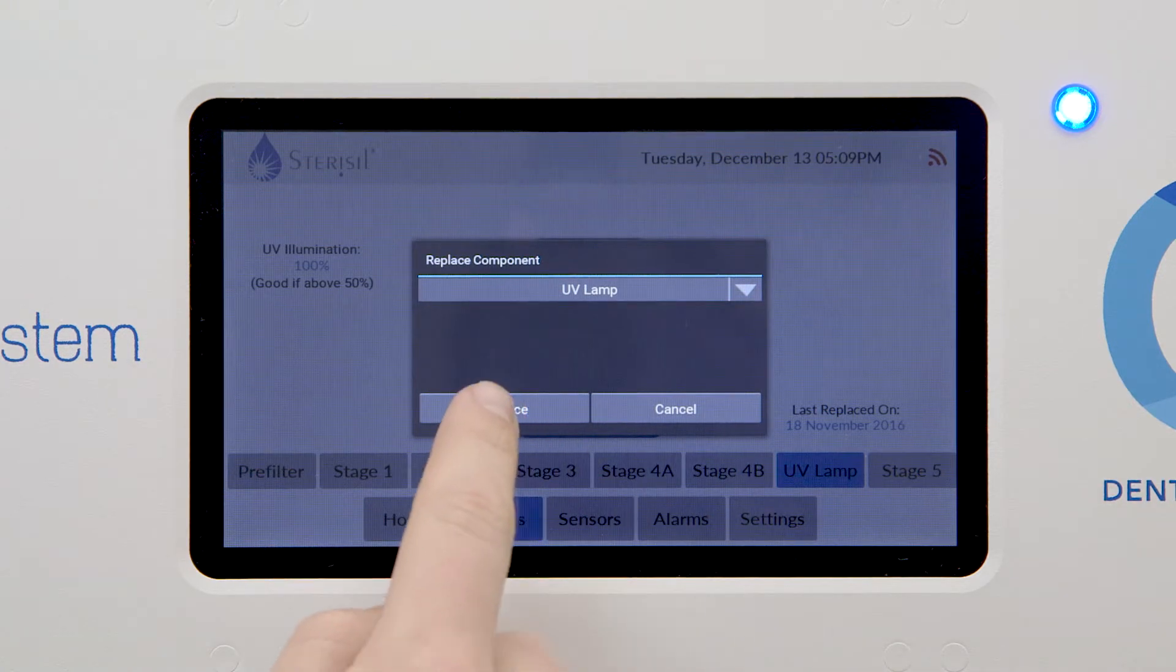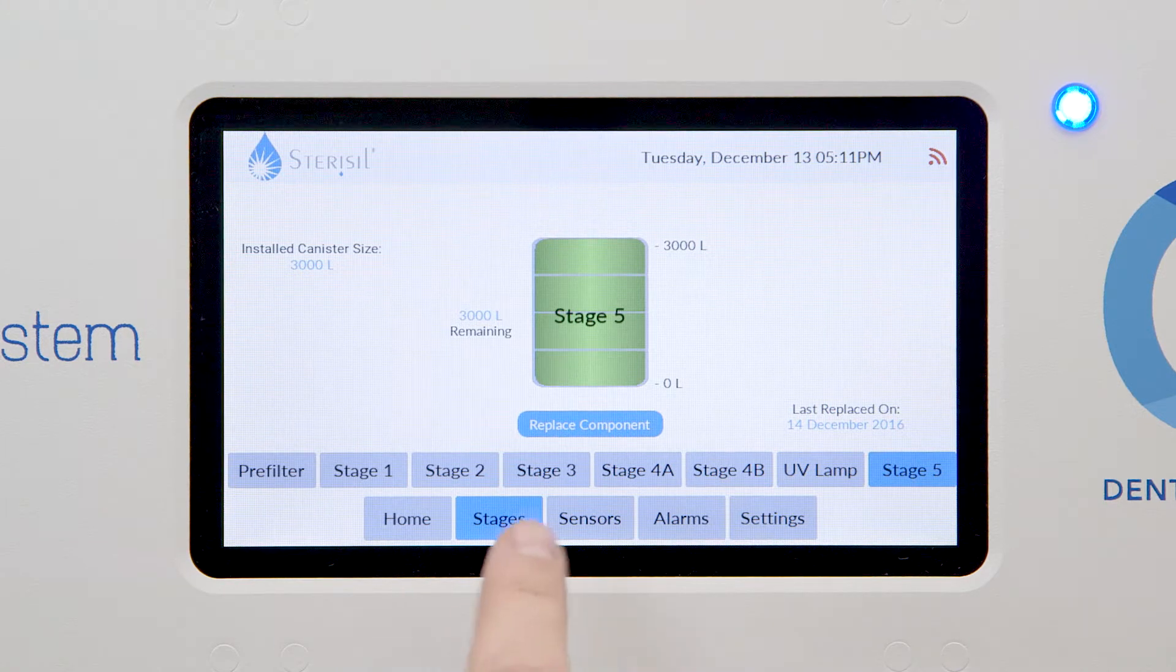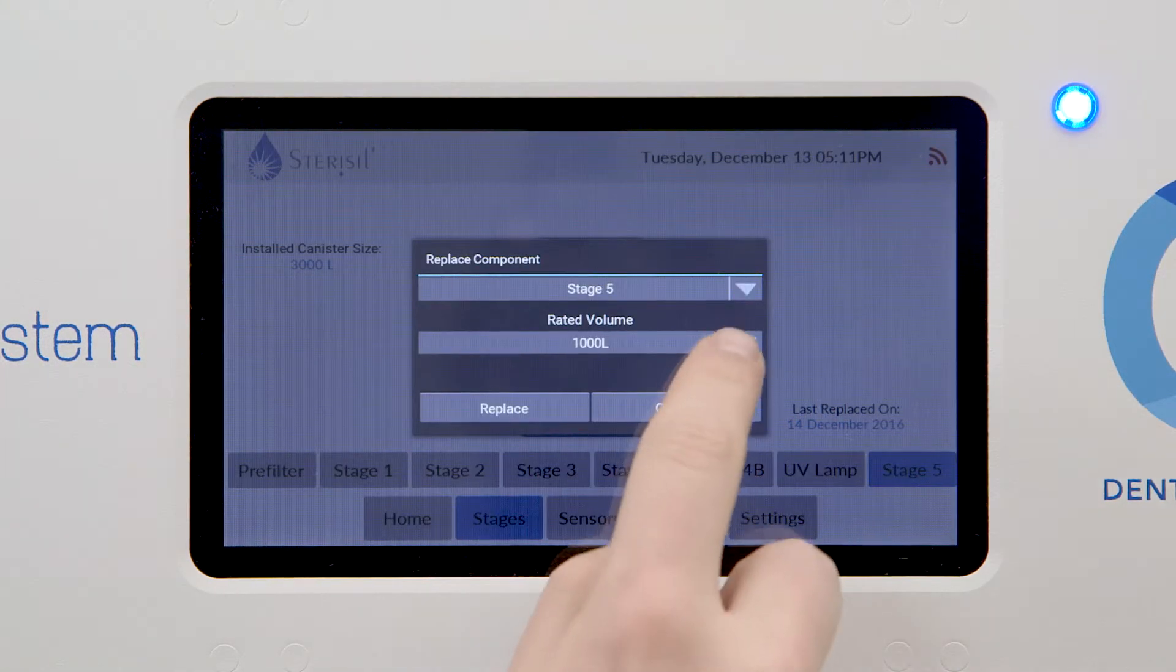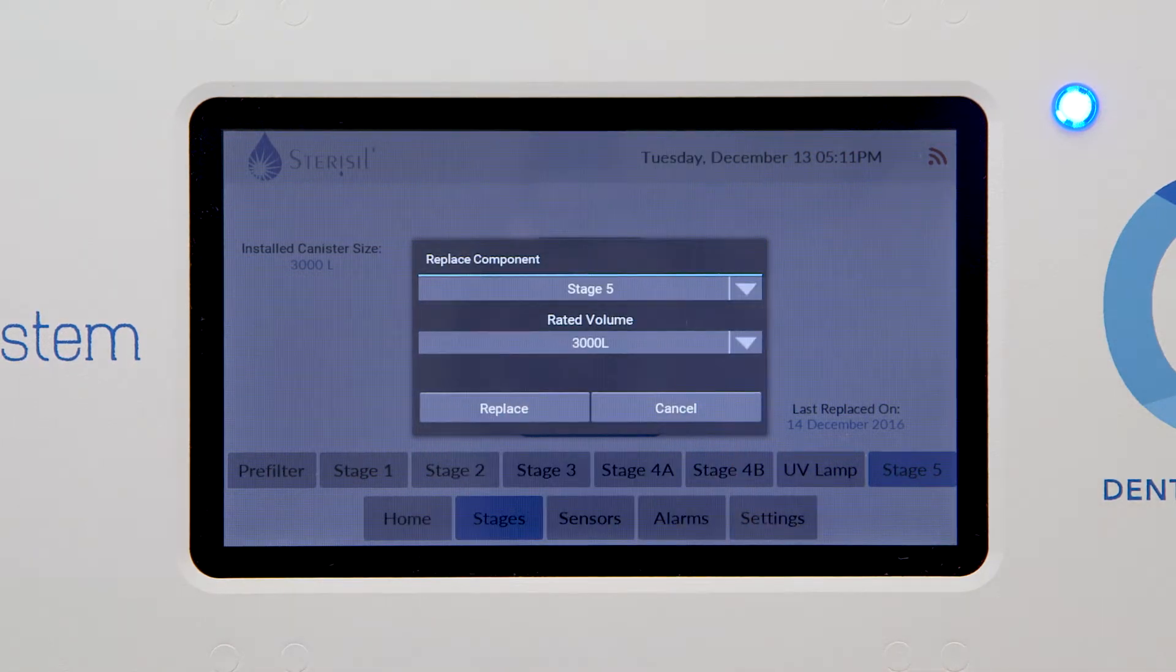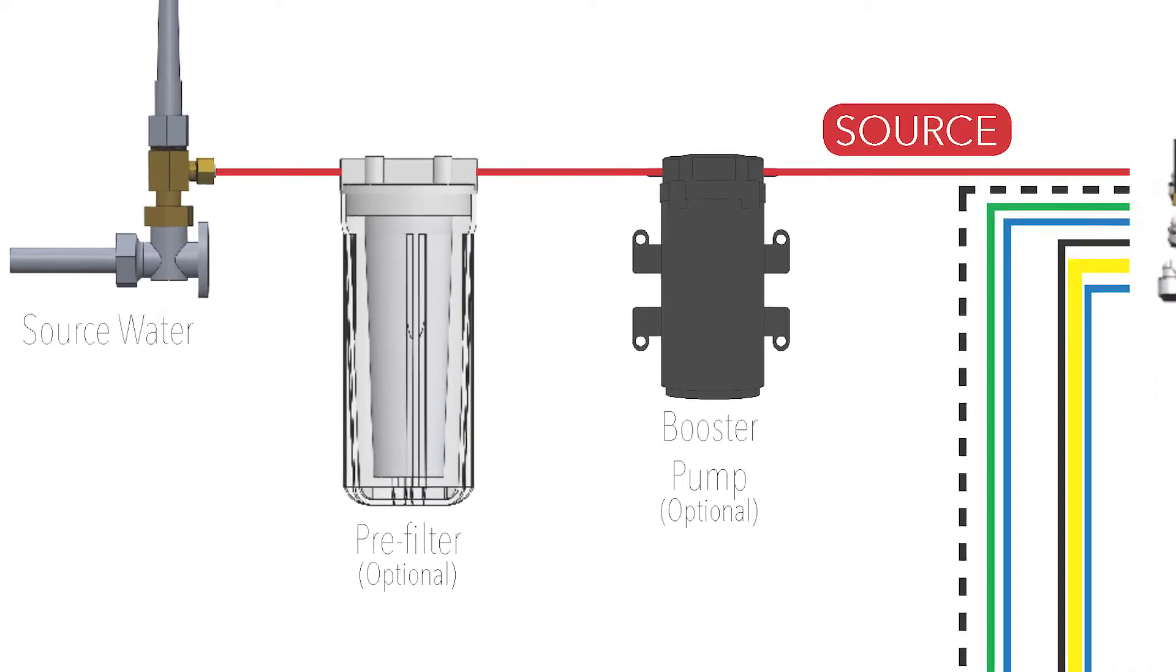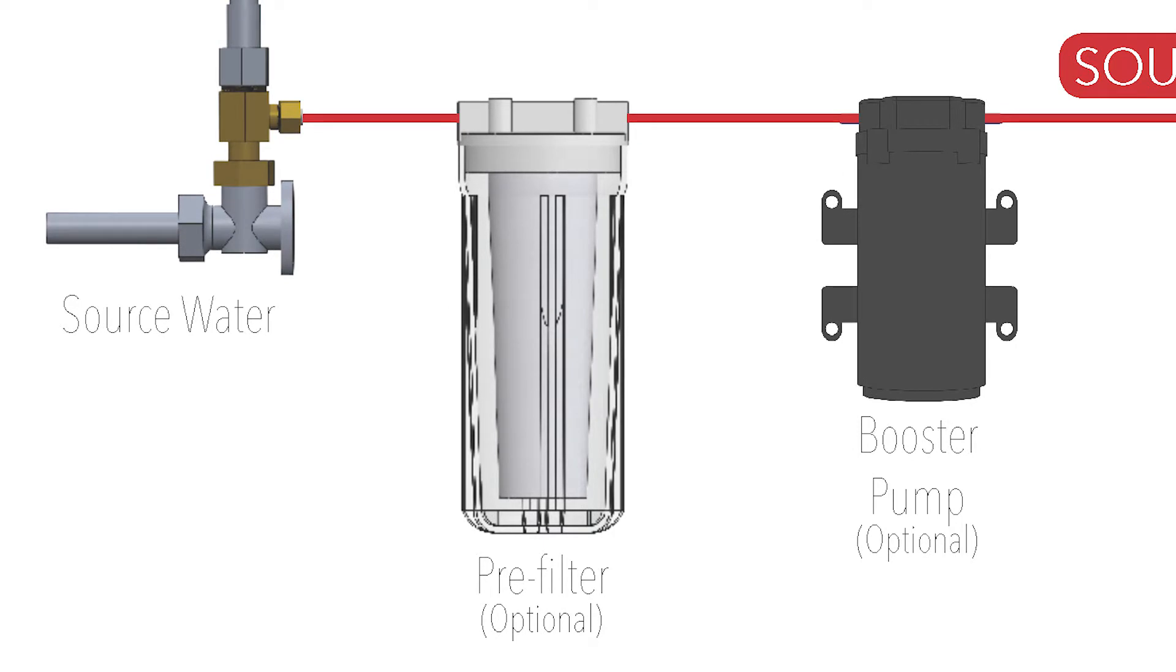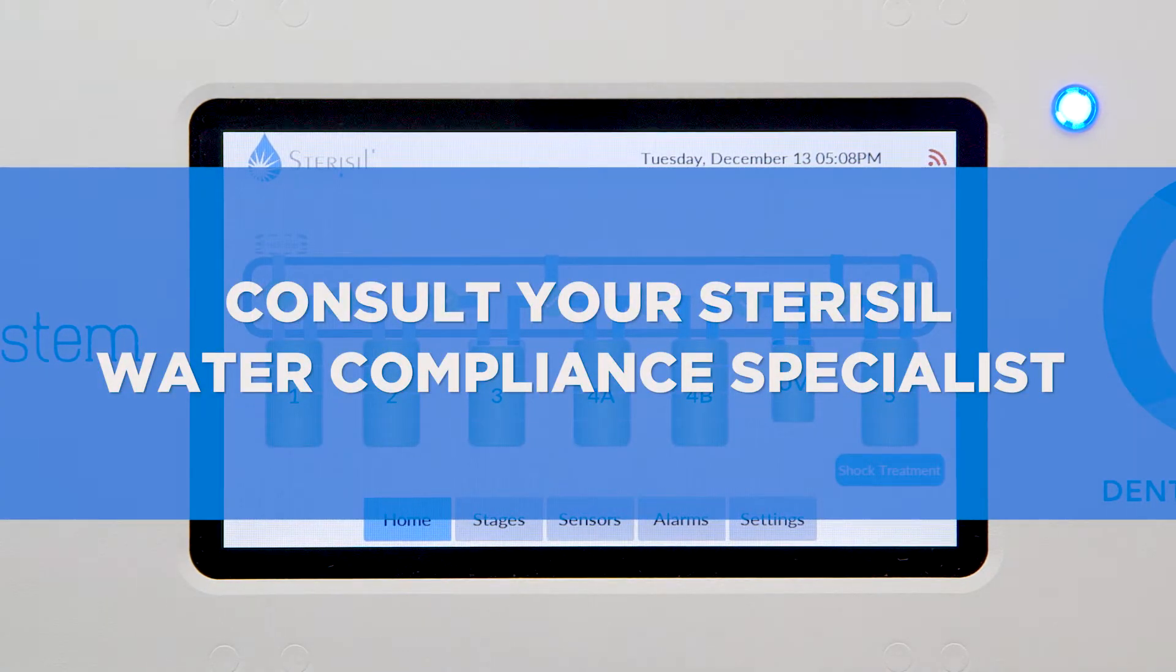Stage five's lifespan is based on a liter count. Each stage five is marked with its liter capacity. From the stage five details screen, verify that your maximum capacity matches the capacity printed on the cartridge. If not, reset the count to the correct number. If your configuration includes an optional pre-filter, you'll need to set the reminder for the appropriate interval. Please consult your Sterisil water compliance specialist to confirm your replacement interval.